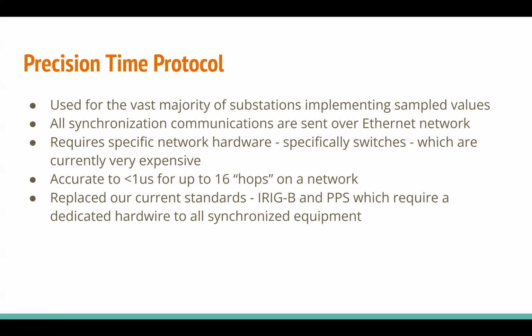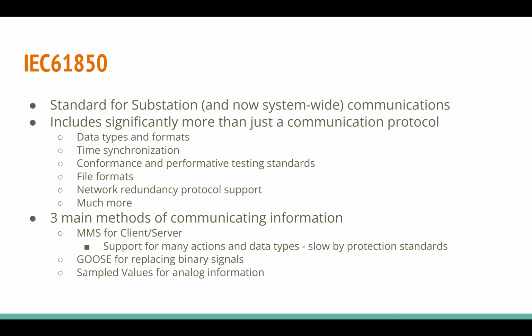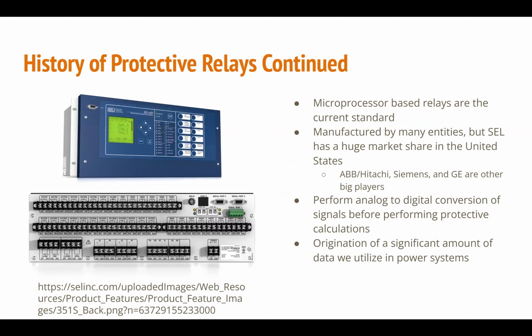So for a conventional substation, we use something else. We use something called IRIG-B or PPS. The problem with both of these is you actually have to run a specific coaxial cable to each relay that you need to synchronize. So I'm going to jump back a few slides here to the microprocessor-based relay again and show you that connection. See this connection right here?